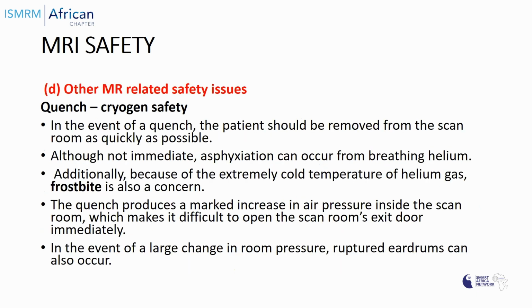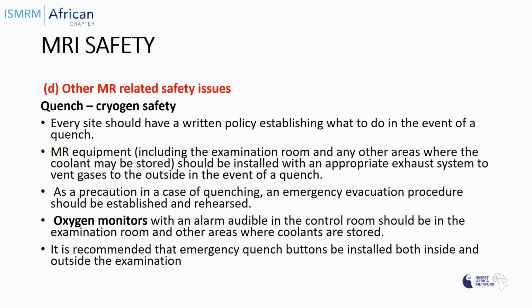In the event of a quench, the patient should be removed from the scan room as quickly as possible. Although not immediate, asphyxiation can occur from breathing the helium. Additionally, because of the extremely cold temperature of helium gas, frostbite is also a concern. The quench produces a marked increase in air pressure inside the scan room, which makes it difficult to open the scan room's exit door immediately. In the event of a large change in room pressure, ruptured eardrums can occur.